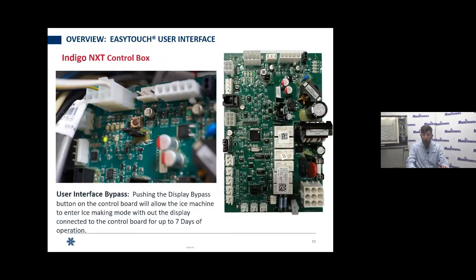So what you do is you push and hold this black button here, and you will hear a click, and you'll see relays light up, which we're going to talk about here shortly. And that will let you know that you're in the display bypass, and you'd see that light there on the right on the control board light up, letting you know that you've bypassed this display. You'd get 7 days of operation before the machine would shut itself back down. This gives you time to go get a part and replace the malfunctioning display and get another one in there.